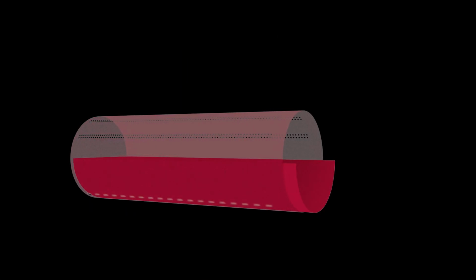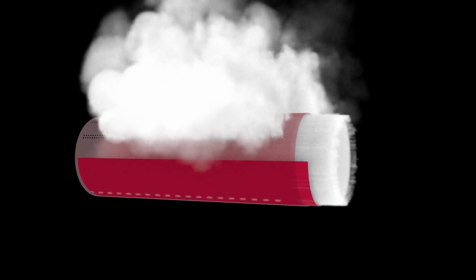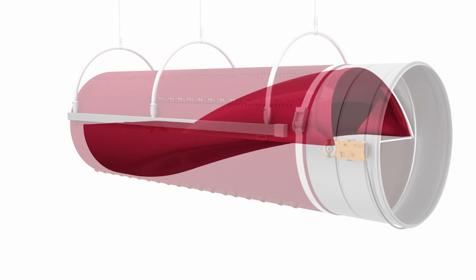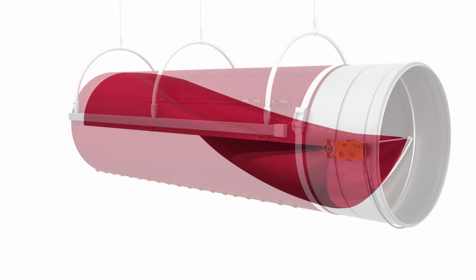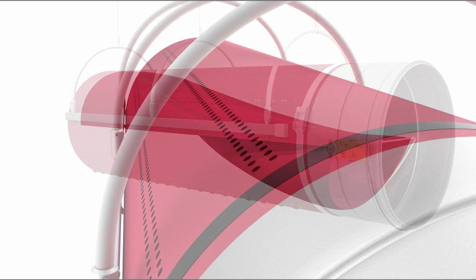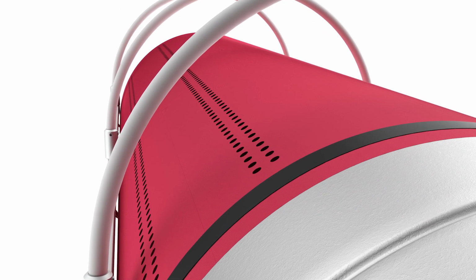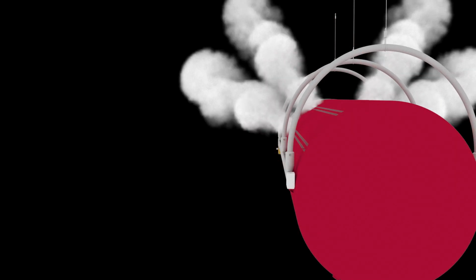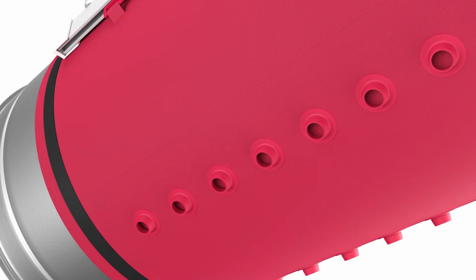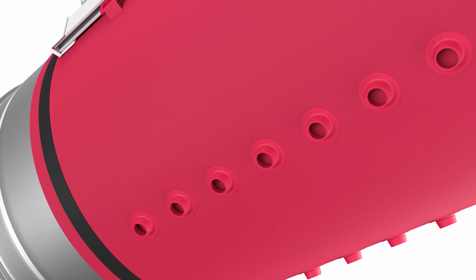The secret lies within. An internal membrane separates two independent flow models, one for cooling and one for heating. They work independently from each other, depending on the position of the damper. The upper section of the duct is tailored for cooling purposes. It has smaller perforations that enable a high air change at low velocity. The lower section is tailored for heating purposes.